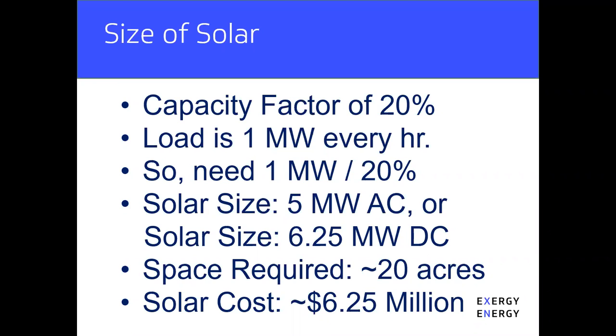So the thing we need to do is take the size of the load, which is 1 megawatt, divide that by the capacity factor, or 20%, and that will tell us our solar size, which in this case needs to be 5 megawatts AC. Now, most solar is quoted in DC, so I take the average of the AC-DC ratios in the United States. So we need to put in about a 6 megawatt solar farm behind the meter in order to recharge our battery every day to be resilient for 24 hours. That requires about 20 acres of space, and the solar is going to cost about $6 million by the time you're done—I'm assuming $1 a watt here for a behind-the-meter C&I space. So it's getting kind of expensive, but it's a lot better than the $43 million for a battery.